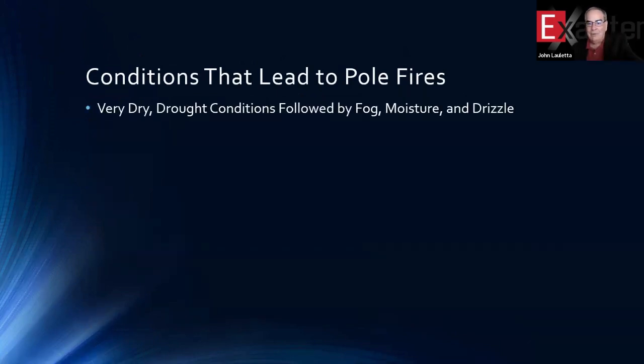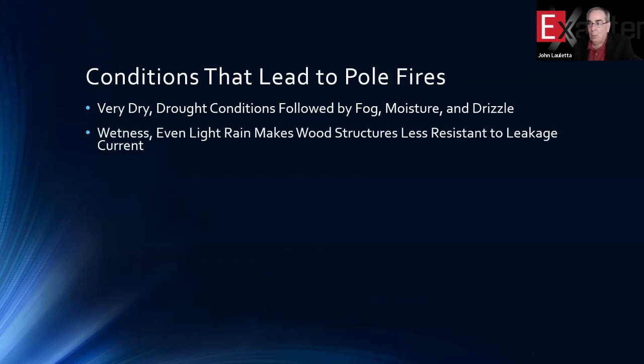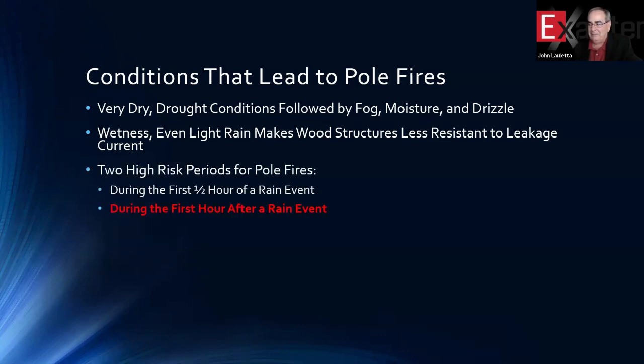So in all of what we've gone through, here are the generalized conditions that lead to pole fires. Very dry drought conditions, followed by moisture. Wet, light rain leaves the wood less resistant to leakage current. So anytime there's a rain event, you have the issue of how well the wood is going to participate in the insulating of the system because of the penetration of the water into the wood.